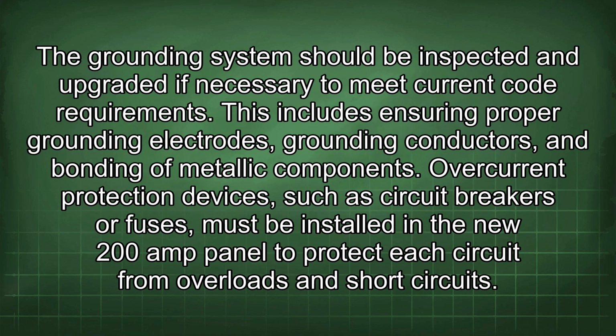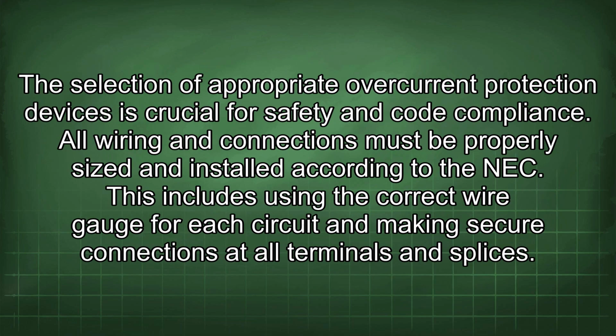The grounding system should be inspected and upgraded if necessary to meet current code requirements. This includes ensuring proper grounding electrodes, grounding conductors, and bonding of metallic components. Overcurrent protection devices, such as circuit breakers or fuses, must be installed in the new 200 amp panel to protect each circuit from overloads and short circuits. The selection of appropriate overcurrent protection devices is crucial for safety and code compliance. All wiring and connections must be properly sized and installed according to the NEC.